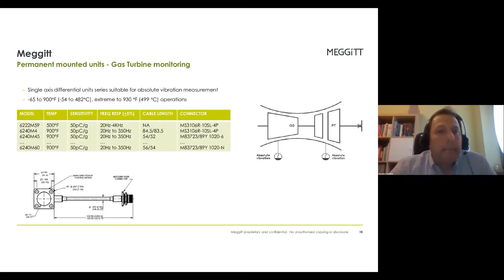Next we have a permanent mounted unit we designed for specific customers. It comes with a variety of cable lengths or connectors. It's not designed to break any particular record, but to be reliable for up to 20 years of continuous operation. Even though it's listed from -54, usually it's around 480 to 500 Celsius operation — very resistant. The application for this one is classical absolute vibration monitoring of a gas turbine.